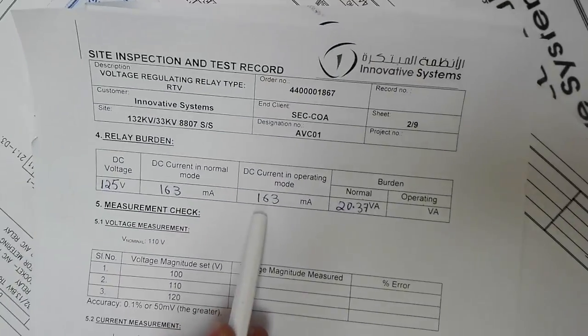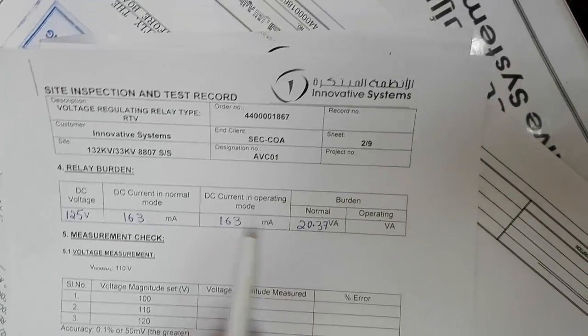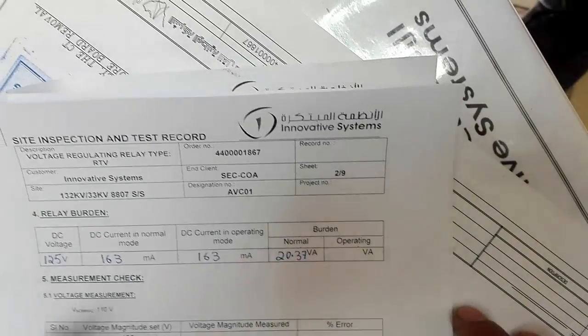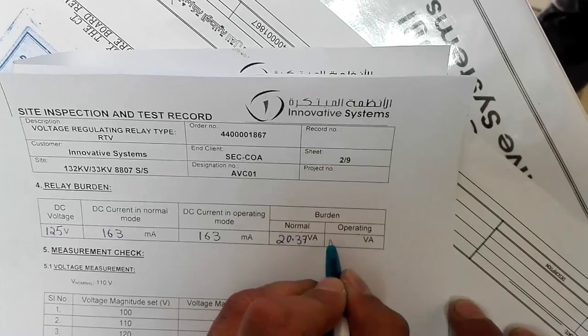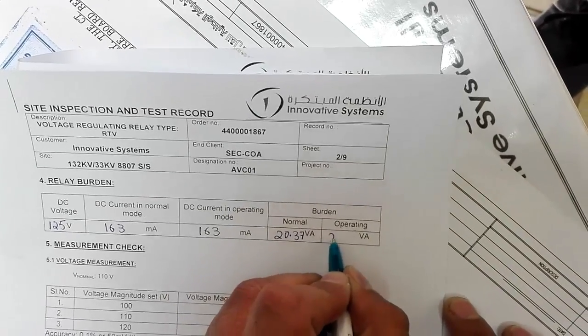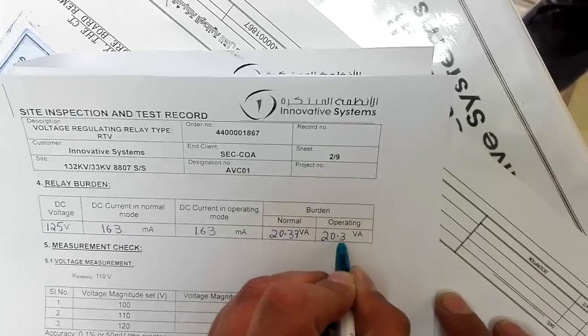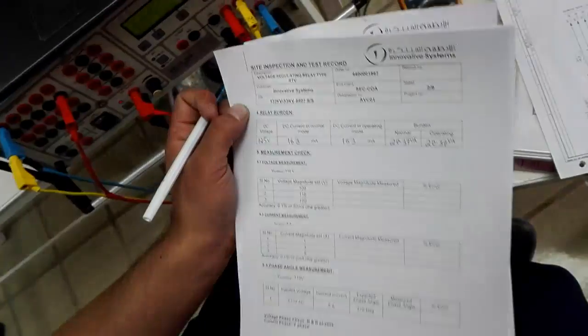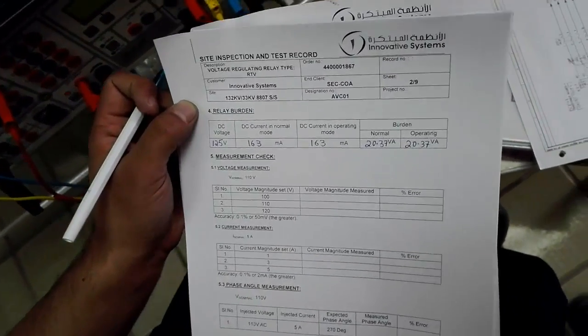Similarly for this, you have to do again the same step, 125 multiplied by 0.163 amps. It will give us the same value, because in normal and operating the currents are the same, 20.375. This was all about the relay burden. Now we have performed the relay burden test.